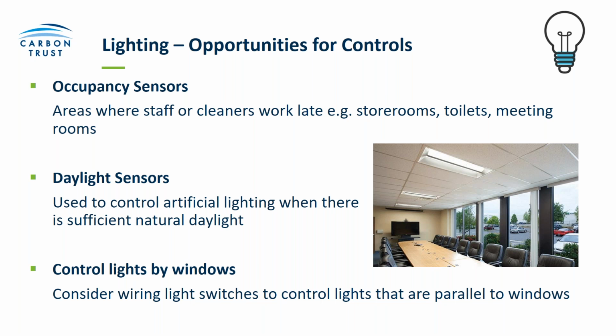Another thing to think about is daylight sensors. Offices often end up being overlit, especially on a sunny day, when you don't necessarily need your lighting on at all, or not as bright. Daylight sensors can sense the lux levels in the office and either turn off or reduce the lighting if there's sufficient daylight. Obviously you need to see properly, but a lot of the time it ends up being far too bright, and people don't think to turn the lights off even when it's really bright outside.